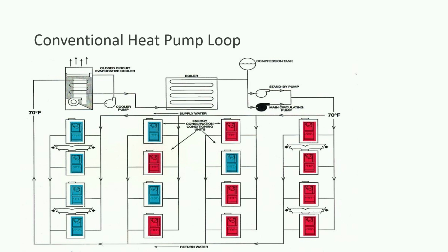Different than a 4-pipe fan coil system where I need to have two sets of pipes, one sending 45 degree water for cooling and one sending 160 degree water for heating. As long as I'm getting 60 to 90 in these two pipes, I can get cooling or heating any day of the week, any time of the year. In the heating season, I'm usually running about 70, and in the cooling season, I'm running 85, 90 degrees.